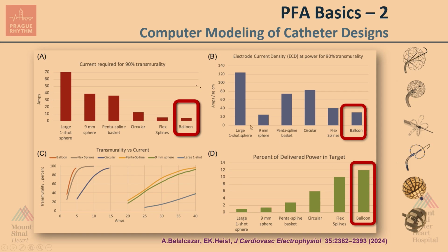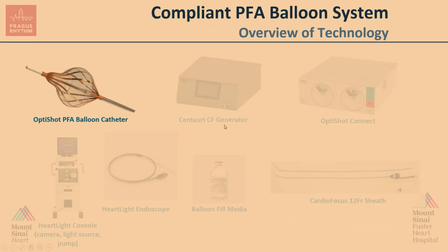Now, there's a caveat to all this, of course, which is you need to make sure that your splines are actually touching the tissue, that you're actually delivered to that target region. And that's where the OptiShot technology has some interesting aspects. And one of the most interesting aspects, beyond the fact that it's a balloon and a central insulator, is that there's an optical endoscope, so you can visually look from inside the balloon at which splines are in contact and optimize that.